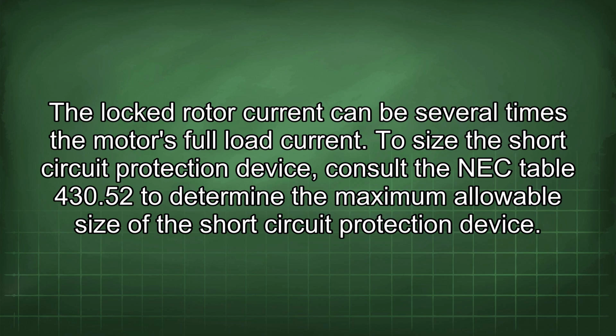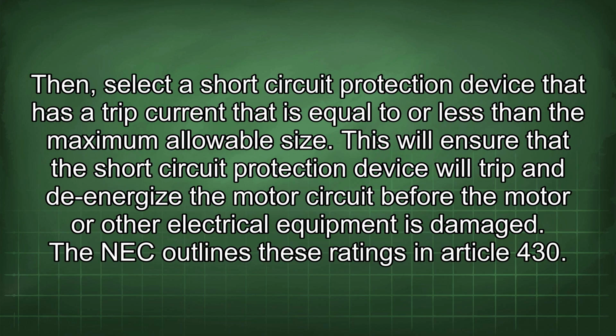To size the short circuit protection device, consult the NEC table 430.52 to determine the maximum allowable size of the short circuit protection device. Then select a short circuit protection device that has a trip current that is equal to or less than the maximum allowable size. This will ensure that the short circuit protection device will trip and de-energize the motor circuit before the motor or other electrical equipment is damaged. The NEC outlines these ratings in Article 430.